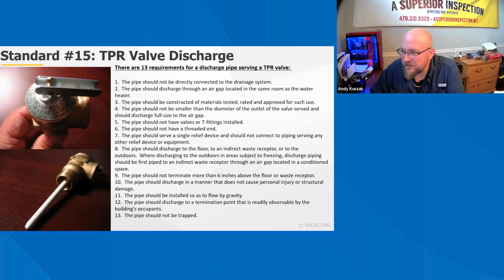An air gap is necessary to prevent backflow and contamination of the potable water system. The discharge pipe must not be reduced in size and must not be less than the size of the relief valve outlet. A reduction in size will act as a restriction and would impede the flow of the discharge.